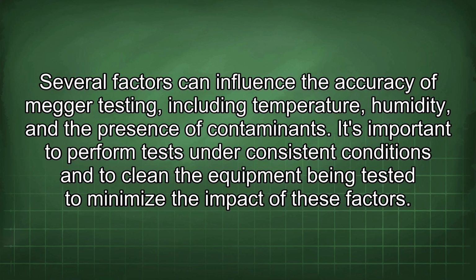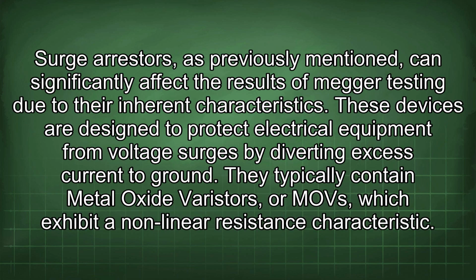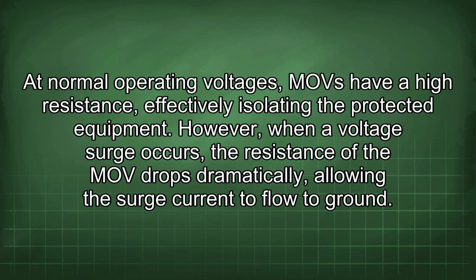It's important to perform tests under consistent conditions and to clean the equipment being tested to minimize the impact of these factors. Surge arrestors, as previously mentioned, can significantly affect the results of Megger testing due to their inherent characteristics. These devices are designed to protect electrical equipment from voltage surges by diverting excess current to ground. They typically contain metal oxide varistors, or MOVs, which exhibit a nonlinear resistance characteristic. At normal operating voltages, a MOV has a high resistance, effectively isolating the protected equipment.